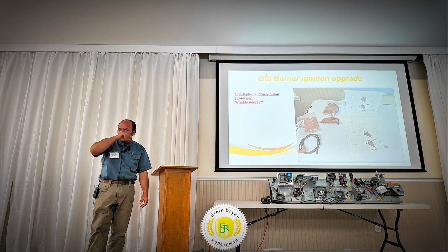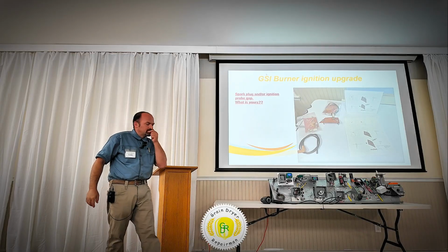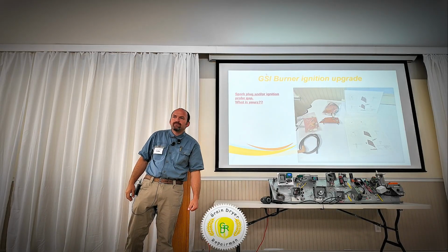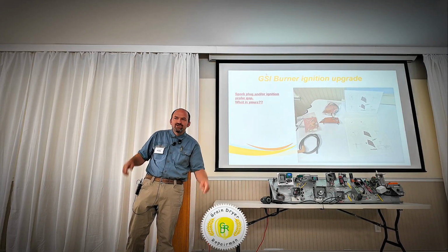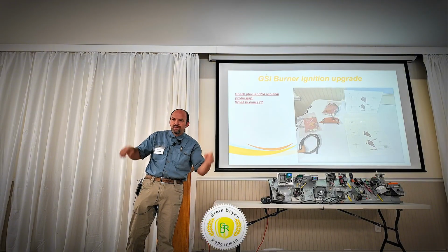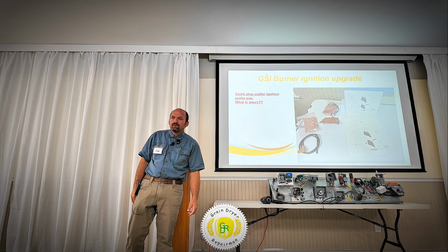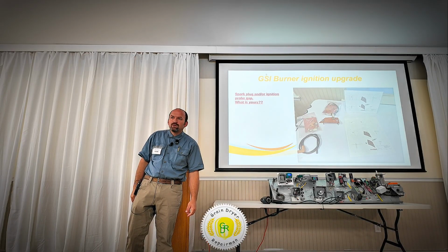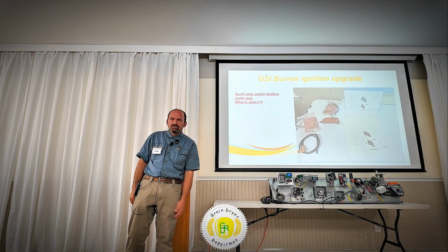Go ahead. I have a quick question about the flame rod. You said to add the second one. Now, tying that in, you just tie it into the jumper wire from one to the other. Jump from one to the other. Yes. Okay, and also on that ground wire, you're saying for that one to ground it out, right? For that igniter, you leave the igniter still grounded though, right? And you just run a ground to the ground bar. Yes, correct. Okay.